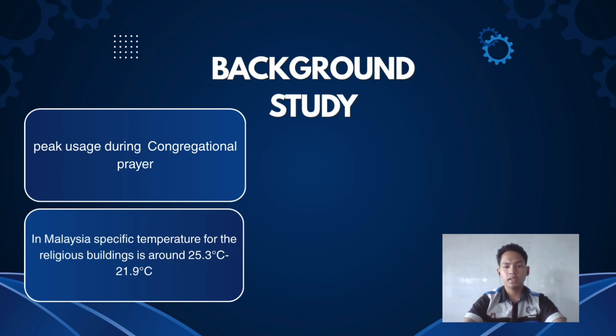Academic literature suggests that the target indoor thermal environment for religious structures in Malaysia should ideally be controlled between 21.9 Celsius to 25.3 Celsius to achieve a balance between human comfort and energy conservation. A major issue right now is operational behavior. Air conditioners are often turned on right before the call to prayer and turned off 10 to 20 minutes immediately after prayers end. This causes indoor temperature and humidity levels to rise rapidly right after shutdown, putting heavy thermal stress on the building structure and reducing operational efficiency.